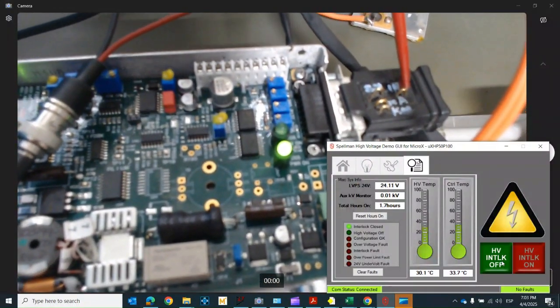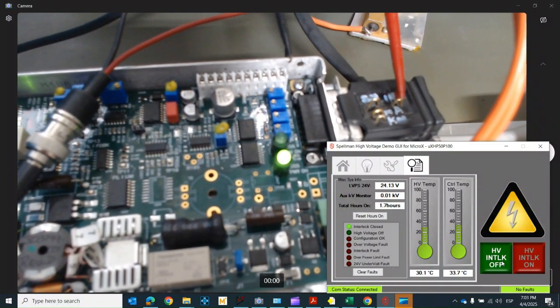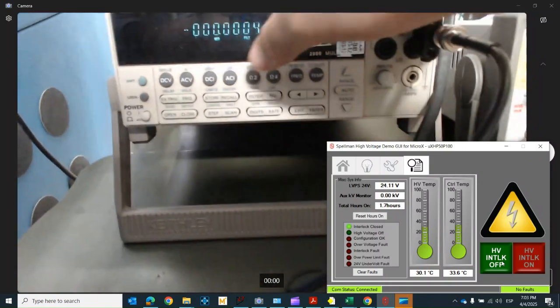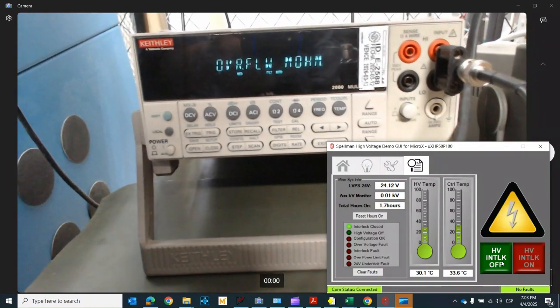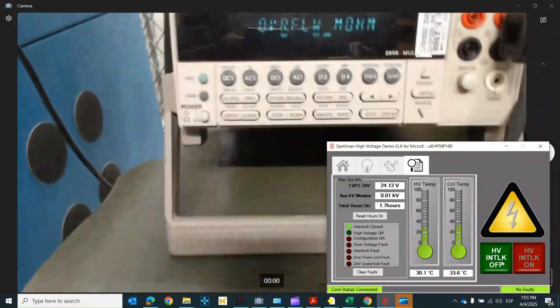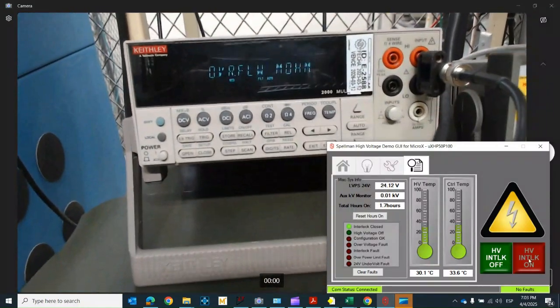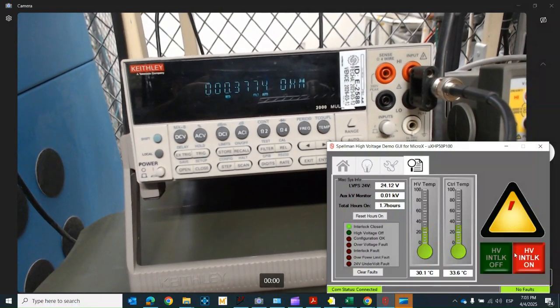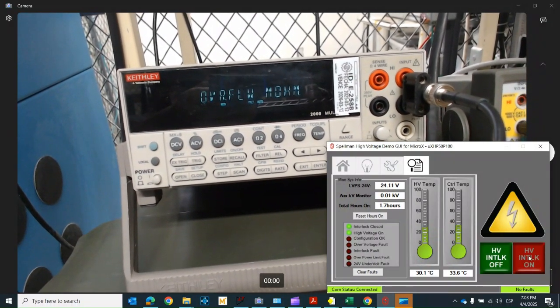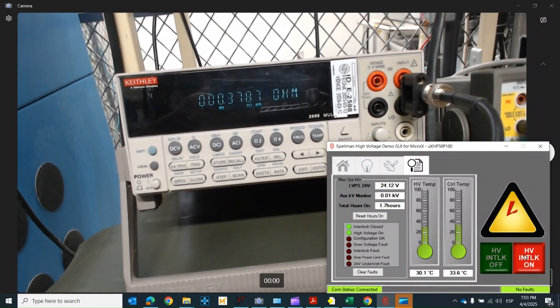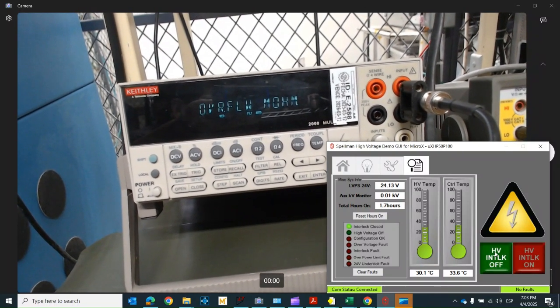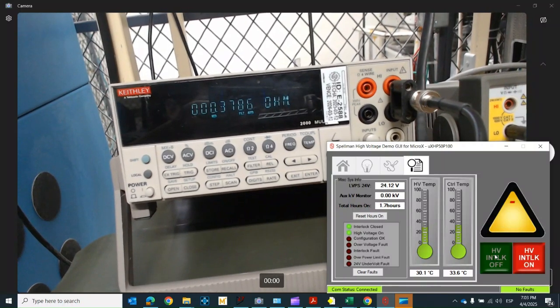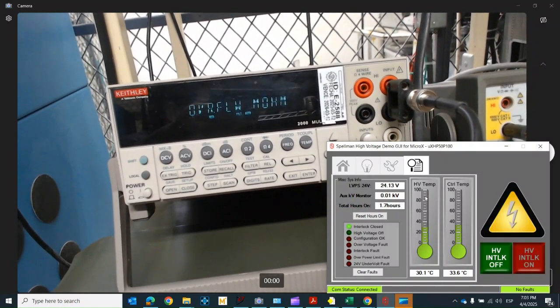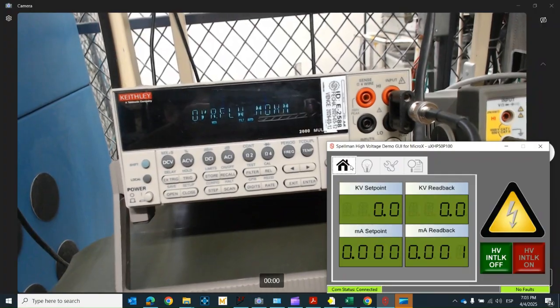After confirming value is 24V, we will proceed to test for the open collector interlock feedback signal. This tests the activation of a MOSFET output that is located at the pin 12 of the 15-pin connector. Signal will be open or off when the interlock is open and will show closed or on when the interlock is closed. Using a DMM in ohms, meter is connected to pin 12 and measuring the resistance across those terminals to confirm operation. In this case, signal is operating successfully. Result to be noted in datasheet.